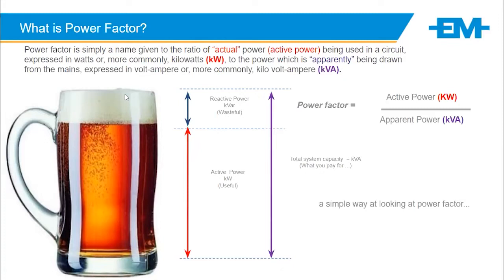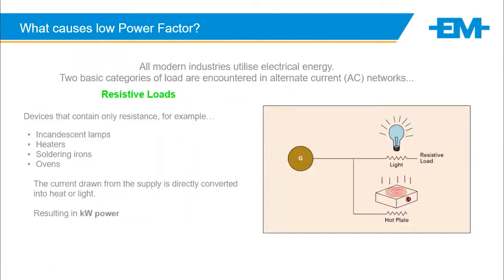All right. The ratio is explained simply by taking kilowatt divided by kVA. A lot of your power meters out there, when you browse the menus, you would see something that refers to PF or COS, and that's what we're going to discuss. So just to get a bit of understanding of what this actually means. So what causes low power factor? There are two basic categories of loads that we know. Load being a consumer on your physical site. So there are two typical types.